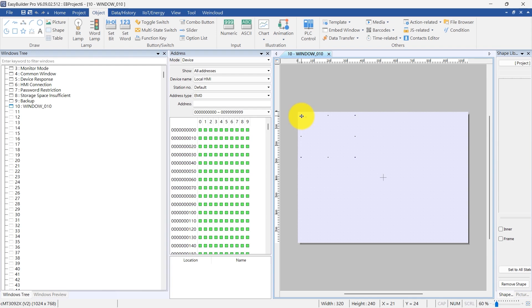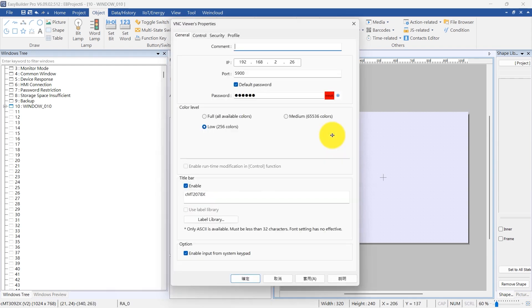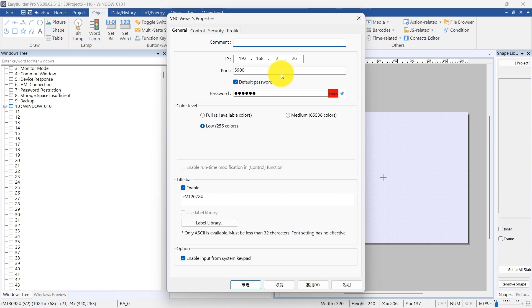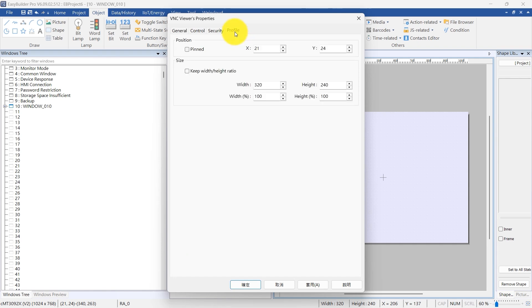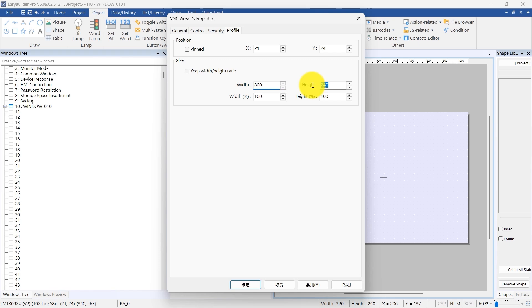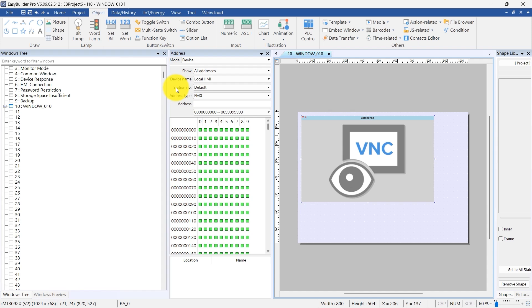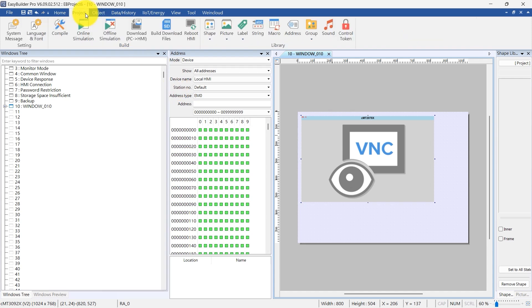With the CMT2078X resolution at 800 x 480 pixels, adjust the VNC Viewer object height to 504 pixels to accommodate the title bar. This adjustment ensures the entire screen, including the title bar, fits correctly, as scaling is not supported in VNC Viewer.